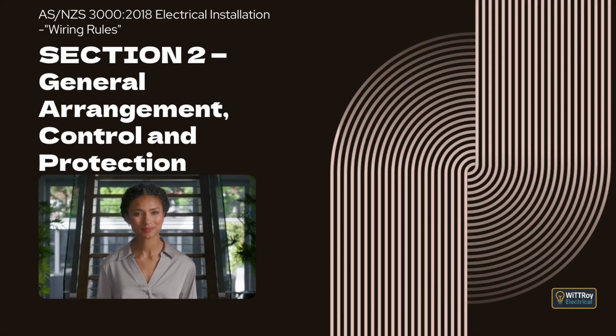This spacing prevents accidental flashover or tracking between different phases or between phase and earth. The distances must match the AS/NZS 61439 series. Smaller clearances may be used only when the equipment is manufactured and tested to its own standard, or when the live parts are insulated from earth in a way that ensures safety.